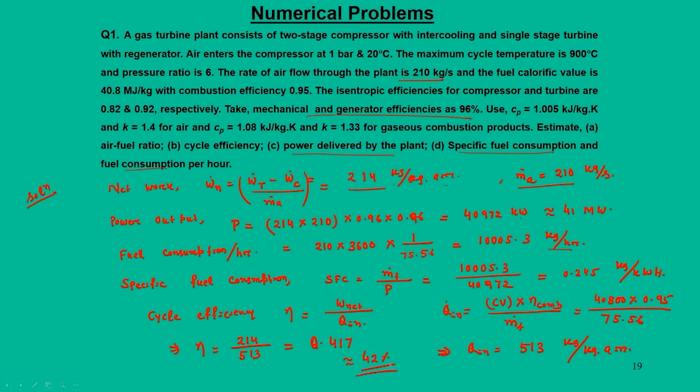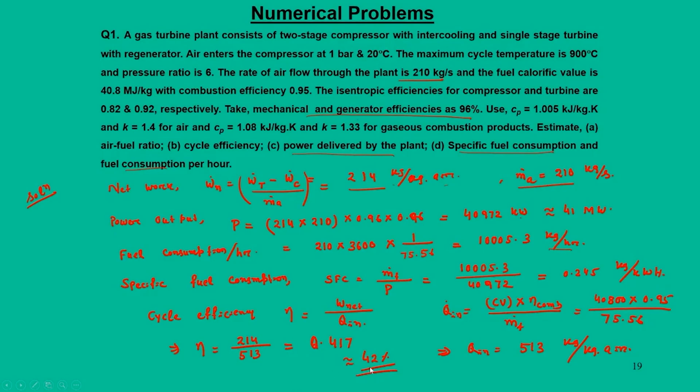So, for a non-ideal cycle, by introducing all these components, the efficiency turns out to be 42%. Typically, conventional gas turbine cycles or ideal cycles have efficiency in the range of 30 to 35%, but through these component introductions the efficiency was improved to 42%.